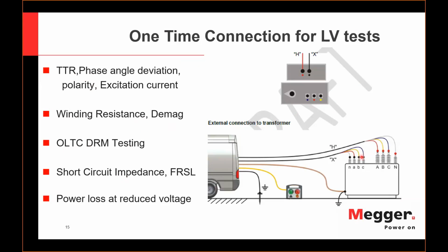Of course, in that case, we will be removing the clamps from the low voltage side, and making a very solid short between the phases ABC on the low side, and making the 50 Hertz short circuit test or a frequency sweep for the short circuit conditions. And we can organize a power loss test at reduced voltage. I will cover that in a separate slide later.